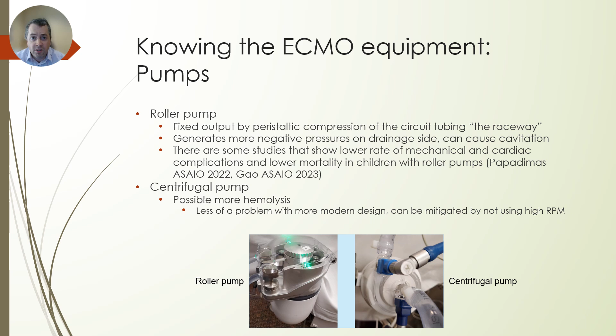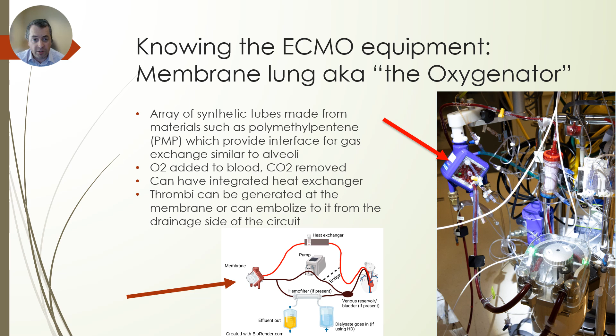The membrane lung, aka the oxygenator, is an array of synthetic tubes made of some polymers, which provide an interface for gas exchange similar to the alveoli. It adds oxygen to the blood, removes CO2, and can have an integrated heat exchanger. This is sometimes where you'll see clots form. This is also where you can see things like condensation develop. When we talk about the troubleshooting steps in the next ECMO chapter, this is fixed by increasing the sweep gas briefly, so-called sighing the oxygenator.